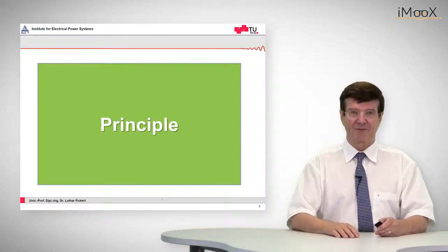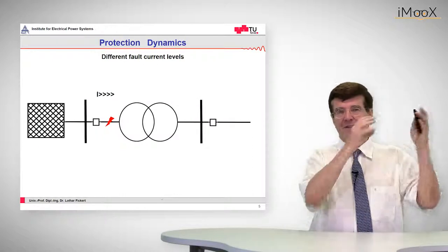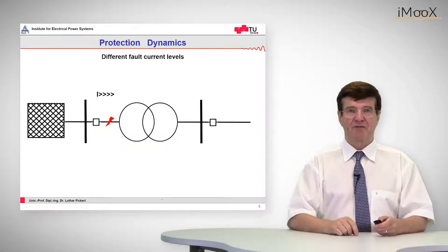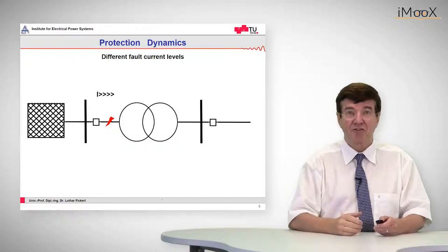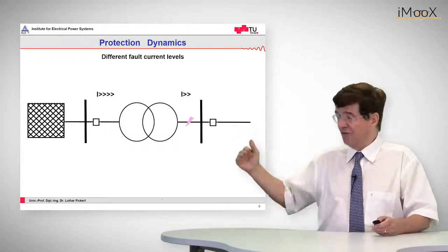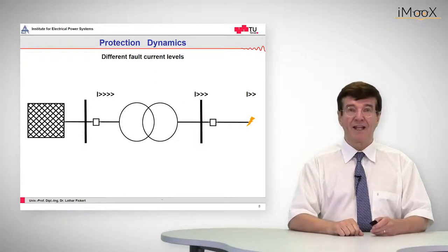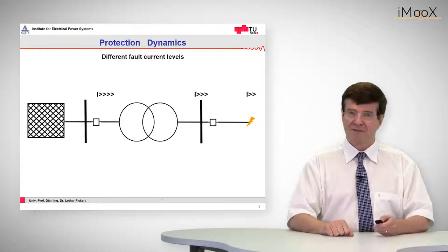First, let's look into the principle. A transformer can be thought of as a lumped impedance between the source and the consumer. We can have faults upstream of the transformer, which are at a very high short circuit level. We can have faults downstream, which have a lower short circuit level, and also faults at the end of a long line.